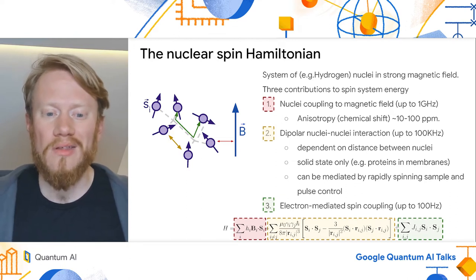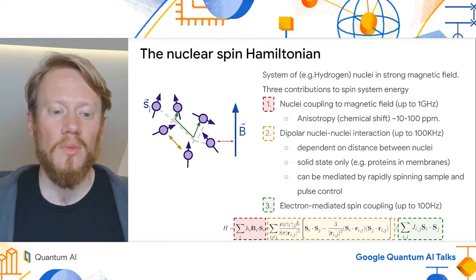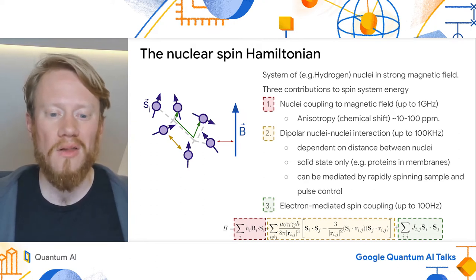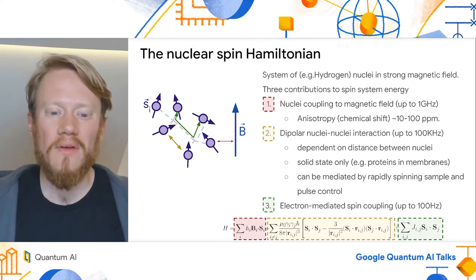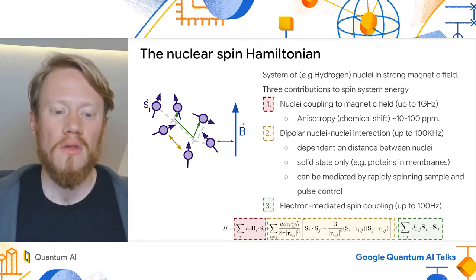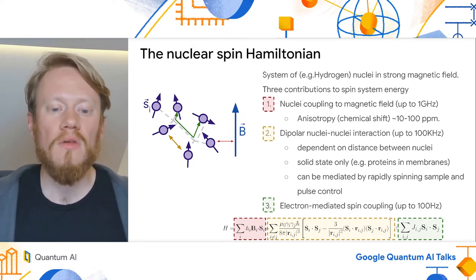These spins experience three main contributions to their energy. The strongest is typically the interaction with the external field, which in an NMR spectrometer can be up to several hundred megahertz. The second largest is a direct dipole-dipole spin interaction, which for protons can be tens of kilohertz, and the third largest is a coupling of nuclear spins via intermediary electrons, which is on the order of Hertz.